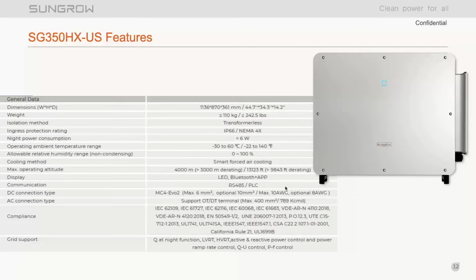The communication is still going to be RS-485 by standard here in North America. And as I mentioned at the top, we are going to be working on releasing a power line communication solution for North America before the end of the year. DC connection type is the same as the SG250. It's going to be the Staubli MC4 Evo 2 connectors, maximum of 10 gauge, but you can go with 8 gauge as one of the options there. That will help mitigate some of the voltage drop that you're going to have if the DC runs are a little longer than ideal. So let us know in the design phase if 8 gauge is something that you're going to be needing for your project.